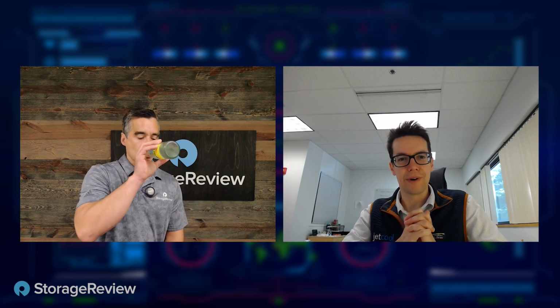Yeah, that's absolutely right. It's not just the high powered chips that people are using Jetcool for, because today with AI and the power consumption from GPUs, there are real constraints in power budgets for a lot of our customers. We have solutions for the 100, 120 and higher kilowatt racks, but a lot of our customers are running at 10 or 12 kW racks. That's their power budget, and it gets back to exactly what you said, Brian: if you have a very power constrained facility or rack, if you can increase the efficiency of the generalized compute of the CPUs, that gives you more capacity to get more compute in. If each server uses 15% less electricity, rough math, every 7 servers you can get an eighth one in that power budget and increase your overall compute output.